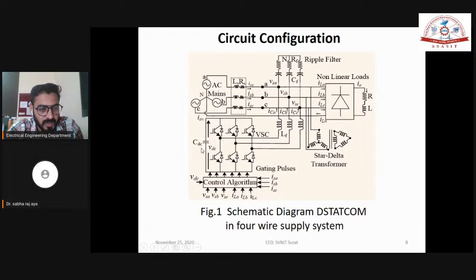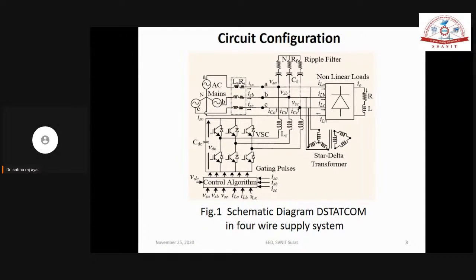If we have this voltage source converter, maybe 3 leg, maybe 4 leg, maybe 6 leg. If 6 leg, it means 3 single phase systems are there. Here we have a 3 leg converter. If we maintain the DC link voltage, VDC, the capacitor voltage, how much? More than the peak value of line to line voltage. Line to line means between AB, BC and CA. Whatever voltage is between those is the line voltage. If we maintain the DC link voltage more than the peak value of line voltage, from that point this voltage source converter is going to work as a compensator.